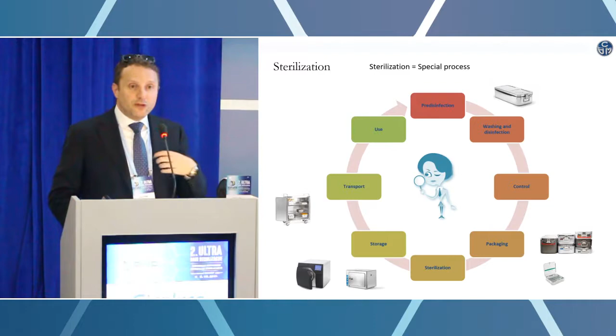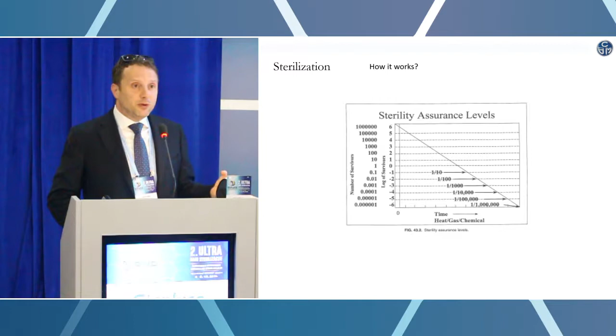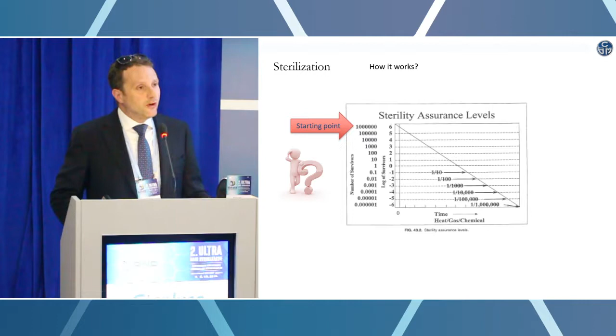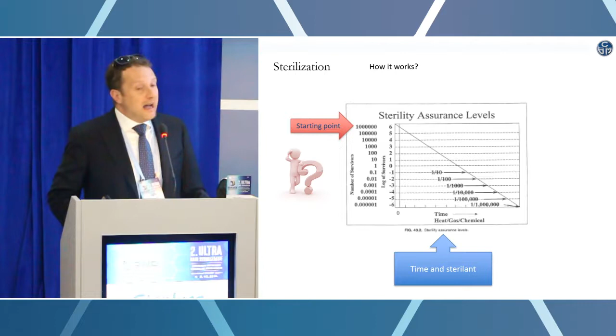So how does sterilization work? We saw a very good presentation this morning. We start from a certain point where we have what we call bioburden, a certain level of infection, let's say more or less, that we don't know. We are not in an industrial environment where we can check how many viable microorganisms we have. So it is tremendously important to reduce this first level as much as possible by washing and disinfecting our medical devices. And then we apply a certain sterilant, and we reach a statistical level of sterility of 1 in 1,000,000 or better.